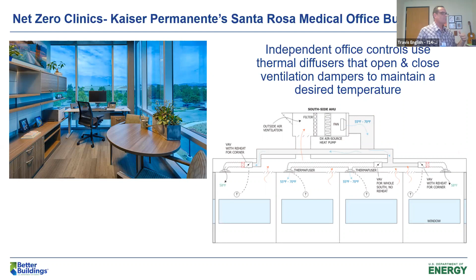Now I'm going to divert a bit and talk about another building, just to talk about natural gas, because it's a big recurring theme in this energy performance gap conversation. I'm not giving you the name of this building to protect the guilty, but on paper this is a heating system that's 95% efficient. In the design energy model, this heating system is 95% efficient. And I'm inclined to believe the manufacturers — I think these boilers are built for, tested for, and validated at 95% efficiency.